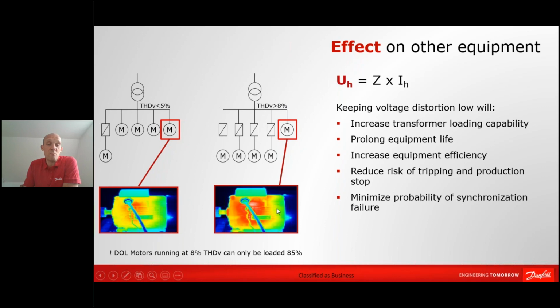And that means that the motor is actually becoming a lot hotter than it was supposed to be. It's running at the same loading condition. Nothing has happened to the motor except that the voltage that the motor is supplied with has a different harmonic footprint. So the voltage distortion is higher in this example, but nothing has changed on the loading of the motor.